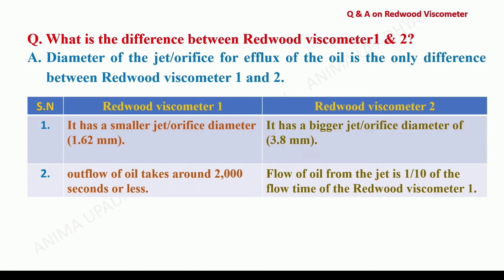What is the difference between Redwood Viscometer number 1 and 2? It is the diameter of the jet or orifice for the efflux of the oil which is different. The diameter of the orifice is only 1.62 mm in Redwood Viscometer number 1 and 3.8 mm in Redwood Viscometer number 2. As a result, the outflow of oil takes around 2000 seconds or less in number 1, and in number 2 it is just one-tenth of the flow time of Redwood Viscometer number 1.